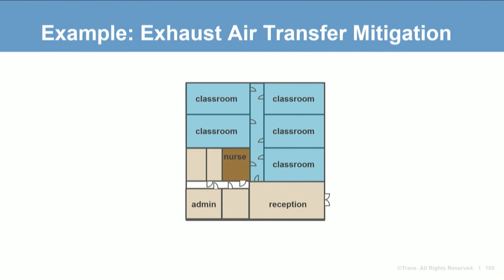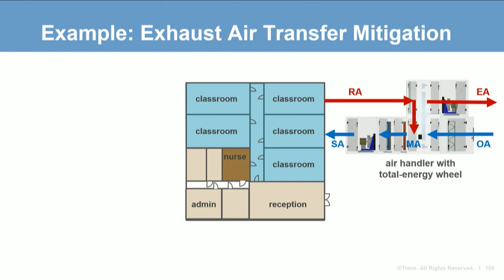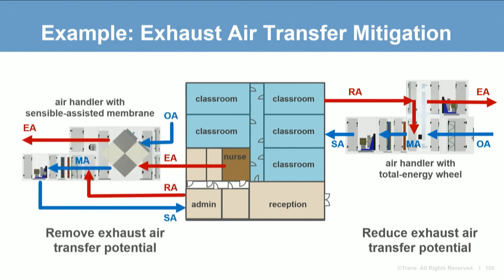Sometimes different thresholds apply in the same building. For example, in an elementary school building, classrooms making up the majority of floor space are served by an air handler with a total energy recovery wheel, designed to reduce exhaust air transfer potential by configuring the air handler to achieve the desired pressure differential. However, for the administrative areas — reception and nurse station — the owner requested to remove the potential for exhaust air transfer, so this area is served by an air handler with a SAM exchanger with exhaust drawn from the nurse station.